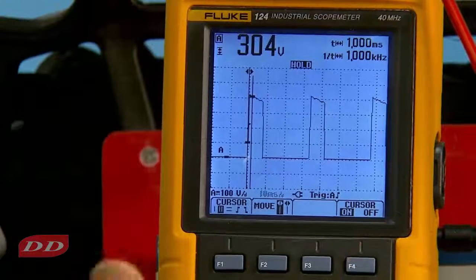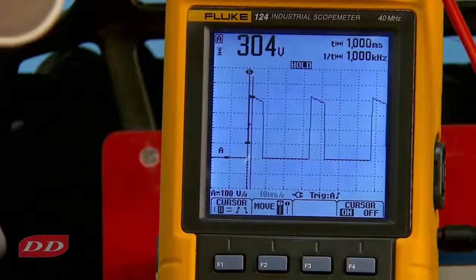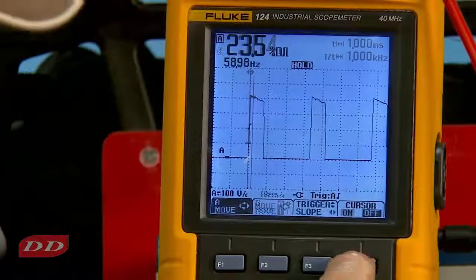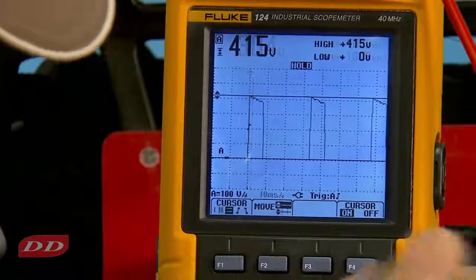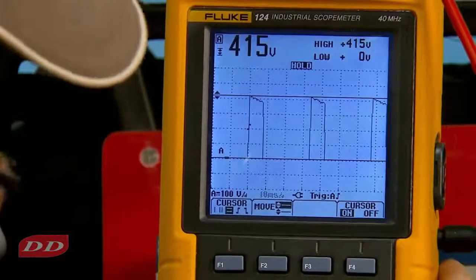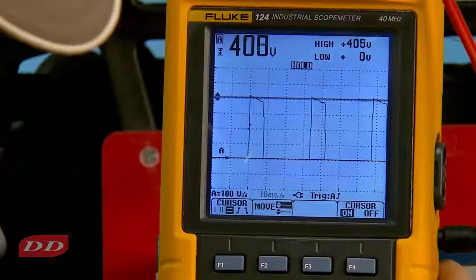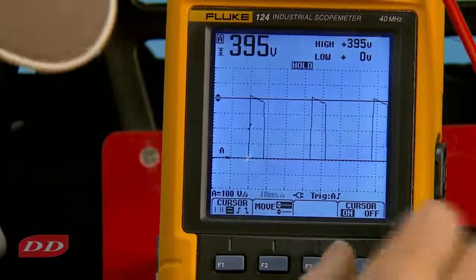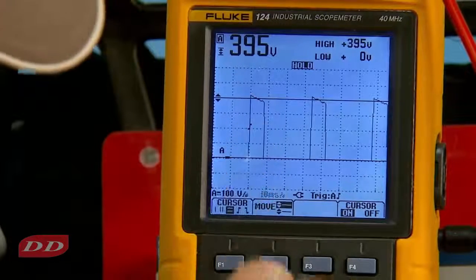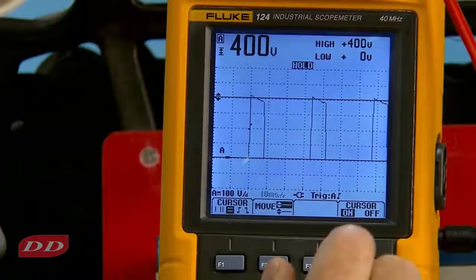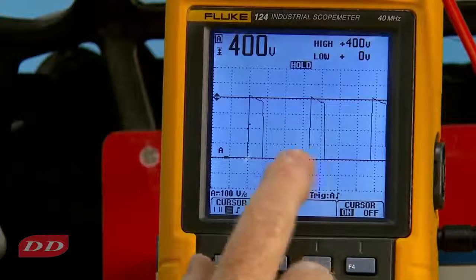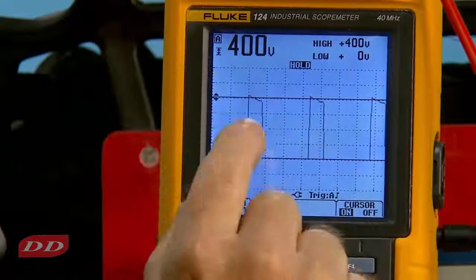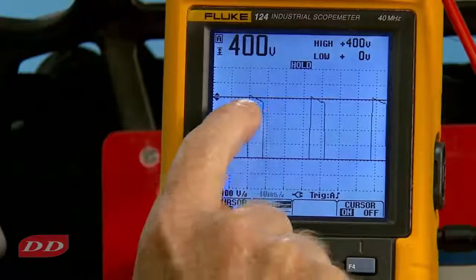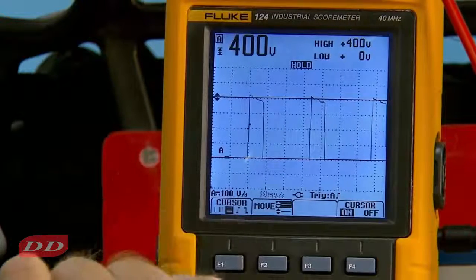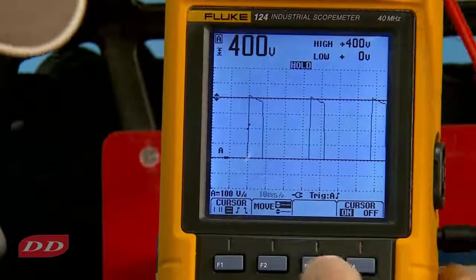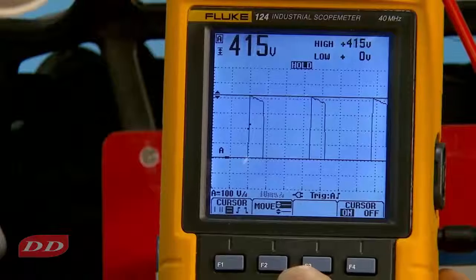And we use that kind of as a rule of thumb, that the fish need at least 1 millisecond of pulse width to react to. So if we bring our vertical cursors down to where the pulse width is about 1 millisecond wide, we're looking at 395 volts peak, maybe 400 volts peak. And that corresponded closely to the voltmeter reading on the unit. So the voltmeter on the unit seems to be reading the peak at 1 millisecond width, whereas the multimeter was reading at about the very peak of the waveform.